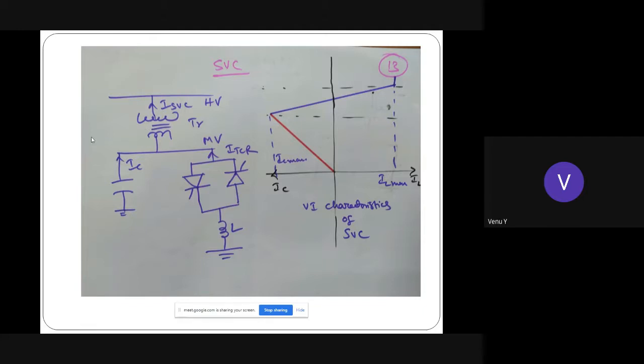All right. So therefore, controlled compensation is provided, and for a fixed capacitor, thyristor controlled reactor type SVC, the size of the TCR is bulky, and I_TCR is a nonlinear current, which is a function of alpha, and hence it injects harmonics into the system. So therefore, SVC not only provides the compensation but also introduces harmonics into the system, so if you want to reduce those harmonics, you need to go for harmonic filters, both active and passive filters.